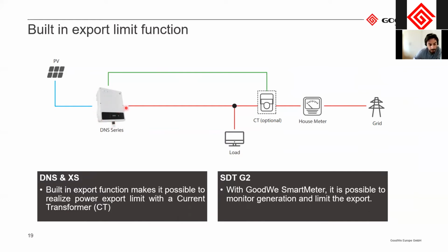And this can be realized with special current transformers that you can get from us. Those current transformers you connect directly to the inverter and then clip them on just before the house meter or the grid connection point, and then they can measure the power flow here to let the inverter know to ramp down or increase the power. And this way, the inverter will make sure that only the loads are supplied and no power is exported beyond this point.